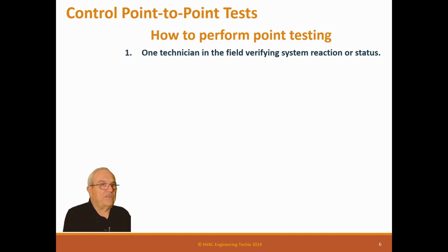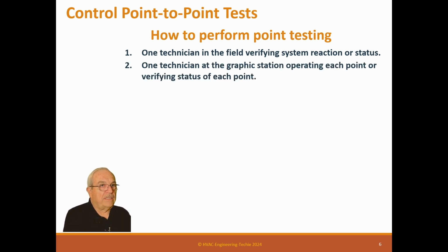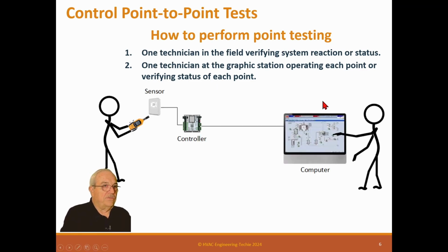So here's how you do it. One technician in the field verifies system reaction or status. Okay, so you got someone in the field with an instrument, and one technician at the graphics station operating each point or verifying status at each point. So here they are, here's the two guys. You got a guy in the field with a calibrated instrument, and he's in communication, normally using walkie-talkies for this. And the guy in the office is looking at the screen.